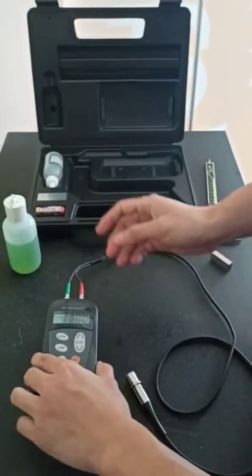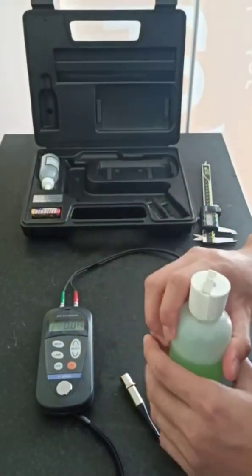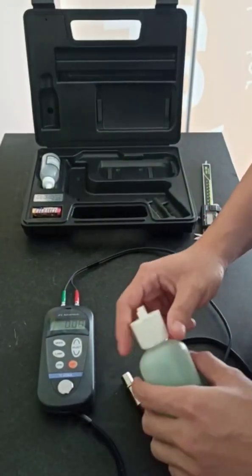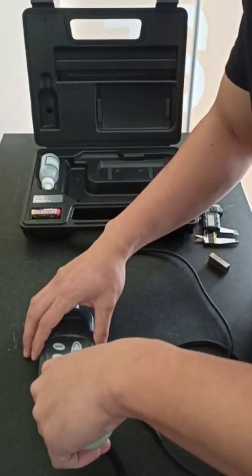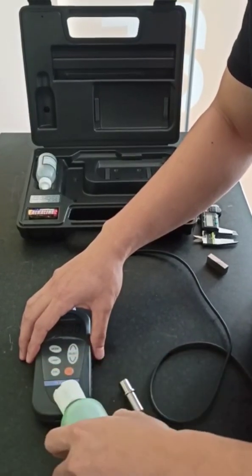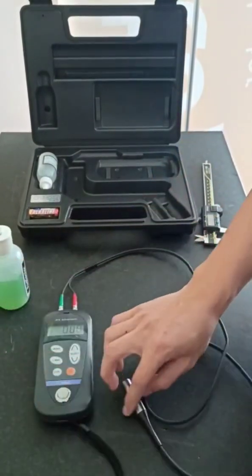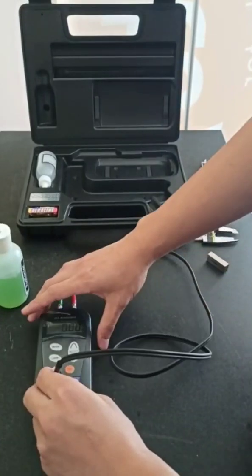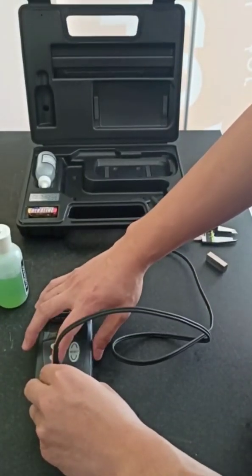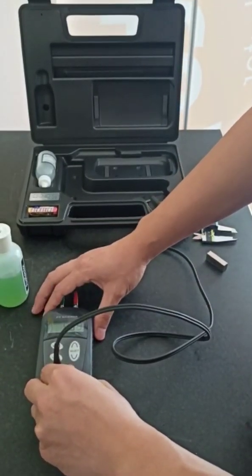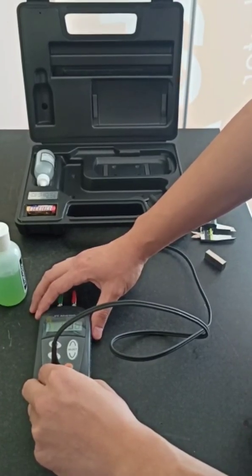After setting that, we apply coupling gel to the surface of the testing plate. Just apply a small amount, then make sure you make full contact with the probe. Press the zero button, wait a few seconds, and it's done.